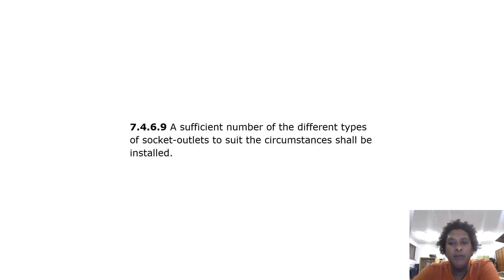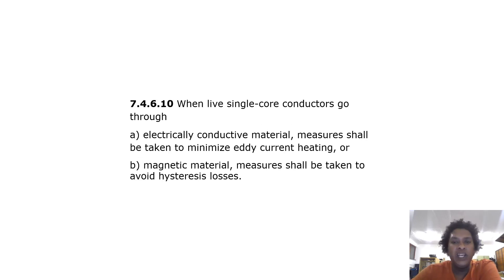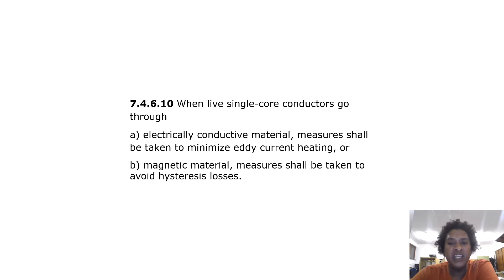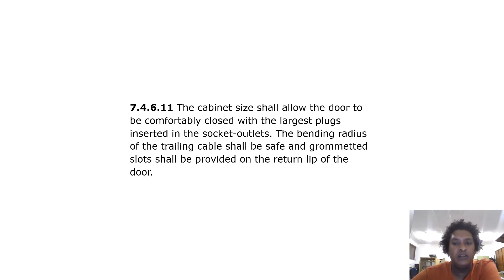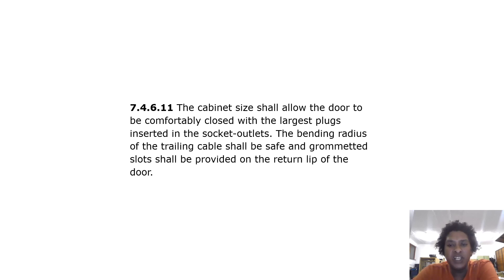A sufficient number of the different types of socket outlets to suit the circumstances shall be installed. When live single core conductors go through electrically conductive material, measures shall be taken to minimize eddy current heating, or through magnetic material, measures shall be taken to avoid hysteresis losses. The cabinet size shall allow the door to be comfortably closed with the largest plugs inserted in the socket outlets. The bending radius of the trailing cable shall be safe and grommeted. Slots shall be provided on the return lip of the door.